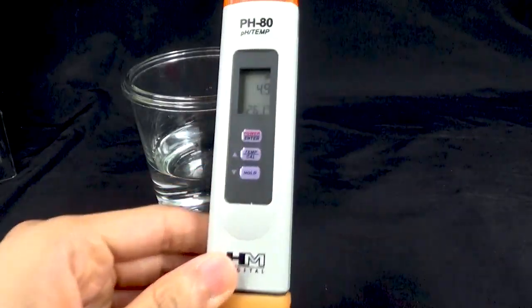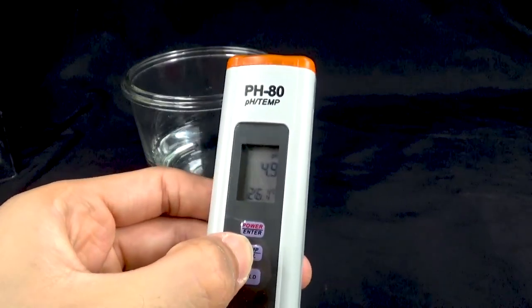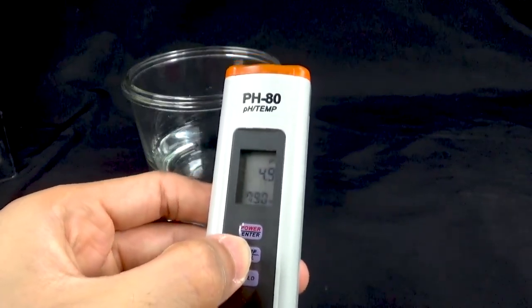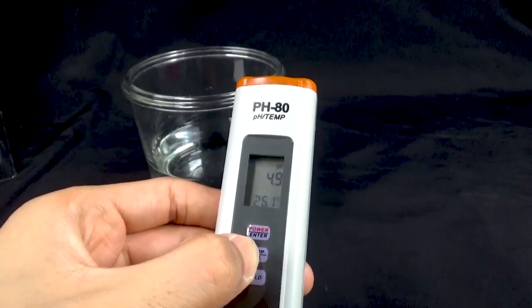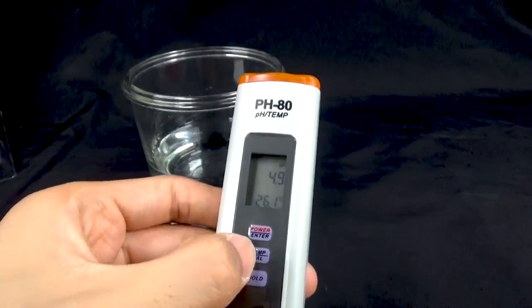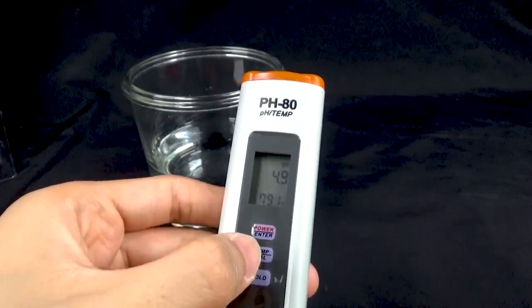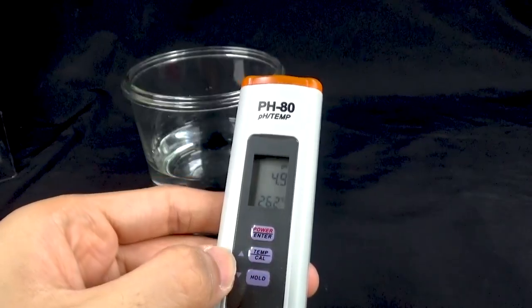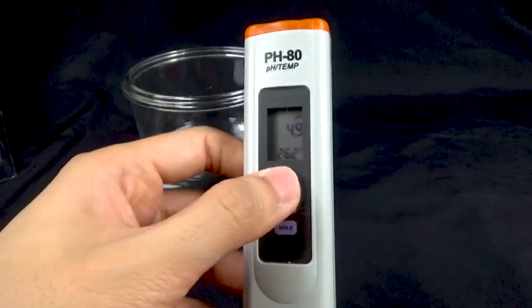The temperature reading is always displayed on the LCD panel simultaneously with pH readings. The default temperature mode is Celsius. To change the temperature mode, quickly press the Temp Cal button to switch between Celsius and Fahrenheit.